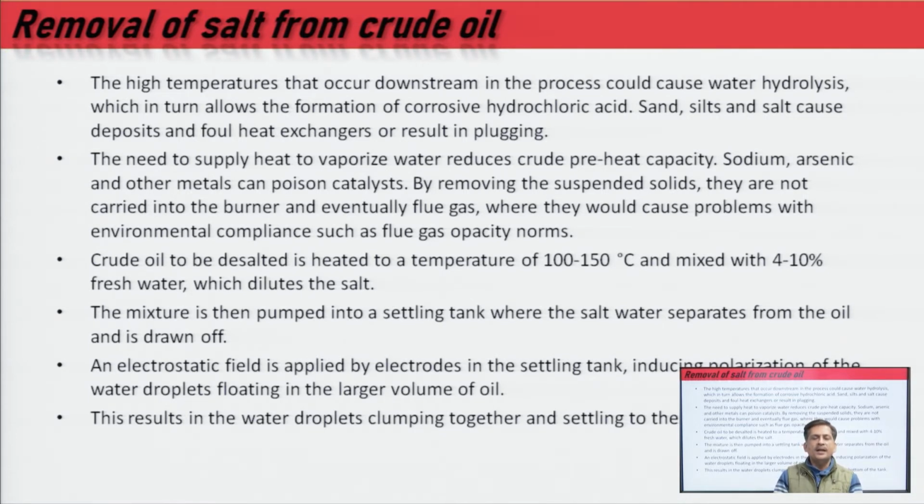The need to supply heat to vaporize water reduces crude preheating capacity. Sodium, arsenic and other metals can poison catalysts. By removing the suspended solids, they are not carried into the burner and eventually the flue gas, where they would cause problems with environmental compliance such as flue gas opacity norms.